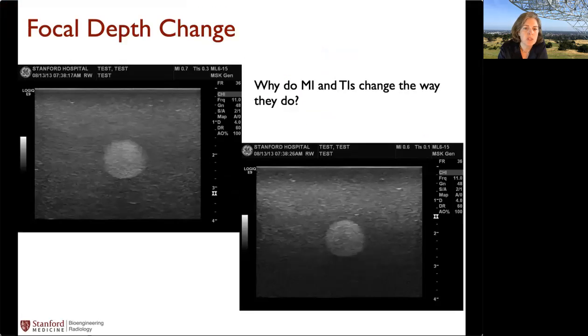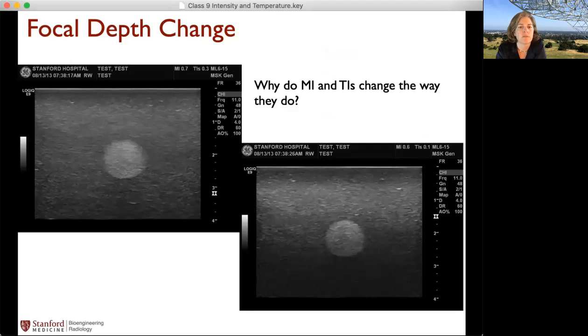Here are some example images in a phantom. Here we have the exact same setup in these two, and the only thing that we've done differently is we've changed the depth. So here it's a little bit deeper, about 3 centimeters, 1 centimeter over here. And our TI has changed from 0.3 to 0.1. So it's gone down as our focal depth is closer in. It was nice that we had this comparison because everything else is the same.